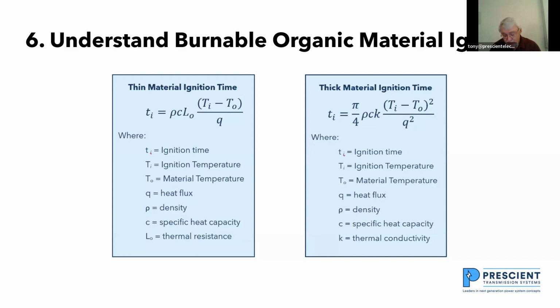And the heat flux, when I'm talking about heat flux, I'm talking about watt seconds per square inch. This is the same as we're looking at for arc flash. When we do arc flash calculations, we do them in watts per square centimeter. That's because the arc flash concepts were all started by chemical engineers. And when I'm looking at organic material, I'm thinking electrical engineers should be doing it. So electrical engineers should be doing it in watt seconds per square inch. And when I'm looking at thick material, the equations are slightly different and the parameters are different.